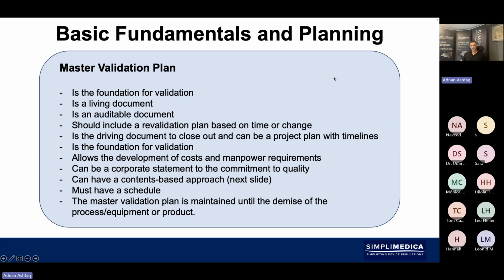It's also an auditable document. And really, in fact, it's usually the first document that an auditor will want to have a look at for validation. They'll say, show us your master validation plan or your validation master plan, and they will go from there. They will look through and usually try and pick out one or two processes, and they would then want to have a look at that in detail to make sure that you've actually performed the process validation for those equipment that have been identified in the master validation plan.